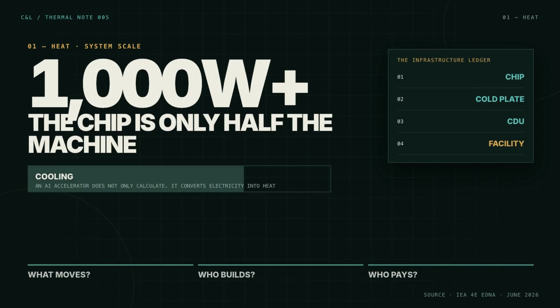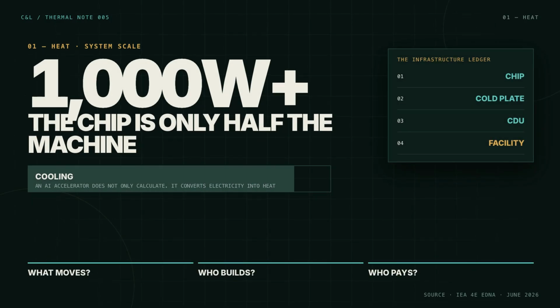An AI accelerator does not only calculate, it converts electricity into heat at extraordinary density. The IEA-4E EDNA report says leading GPU thermal design power now exceeds 1,000 watts per chip, and that liquid cooling is becoming a prerequisite for high-density AI deployments. That creates a second market beside the processor.